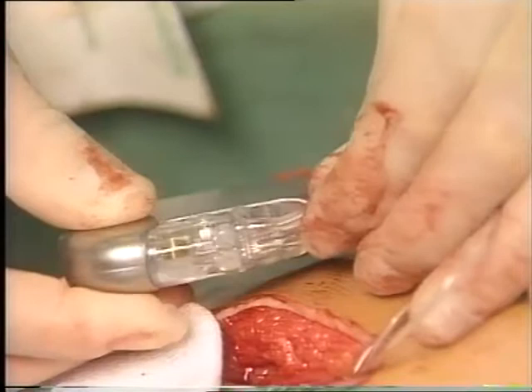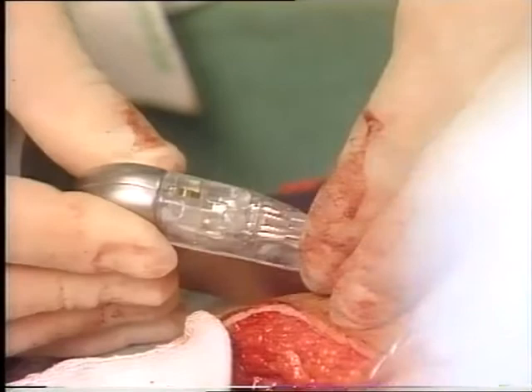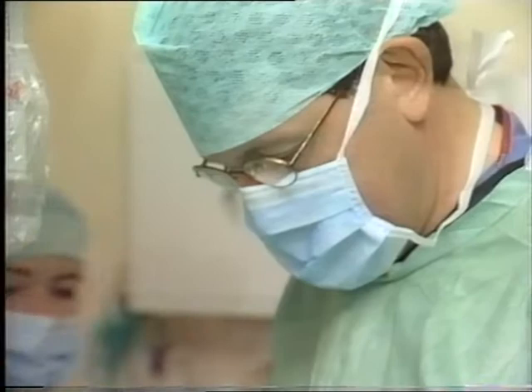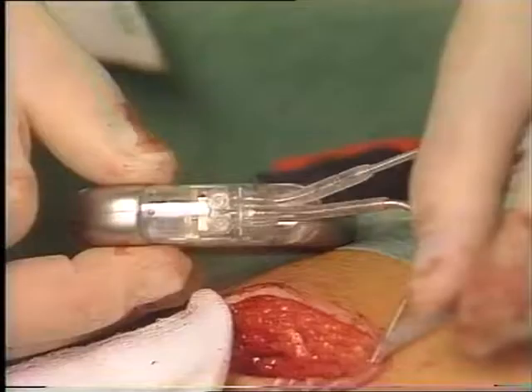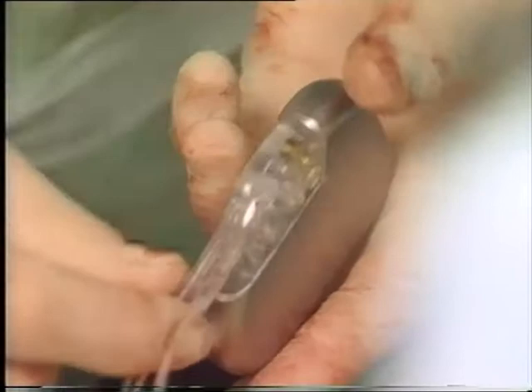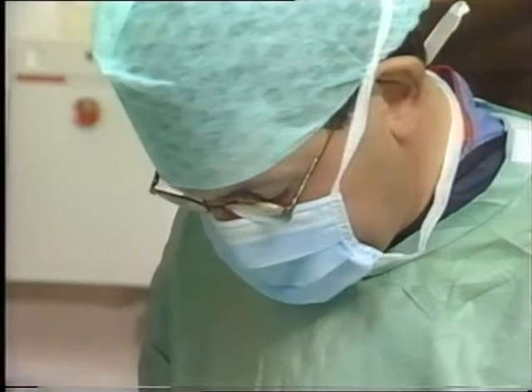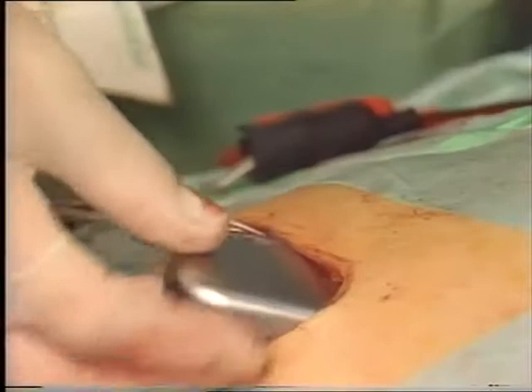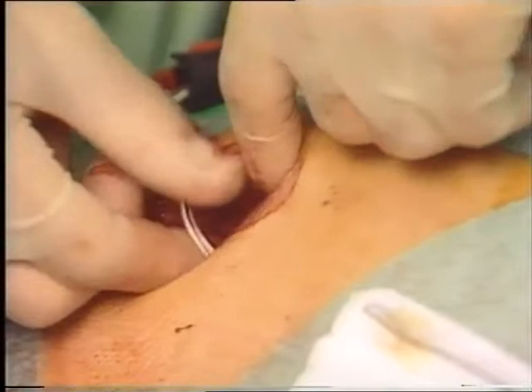The device is designed to be placed and programmed by physicians, with techniques similar to those used for implanting pacemakers. The implantable atrial defibrillator is put in the body rather like a pacemaker — it's just placed beneath the skin, and it's connected to the heart via three wires that go through the veins to the heart. It recognizes atrial fibrillation automatically and charges its capacitors, then discharges with a synchronized shock — synchronized meaning it's given at the same time as the ventricles are depolarized. The shock converts the patient back to normal or sinus rhythm. And if the rhythm is a bit slow following the shock, there is backup ventricular pacing. There's also a facility for the device to store electrograms and various other pieces of data about the arrhythmia and about the success or otherwise of the device.